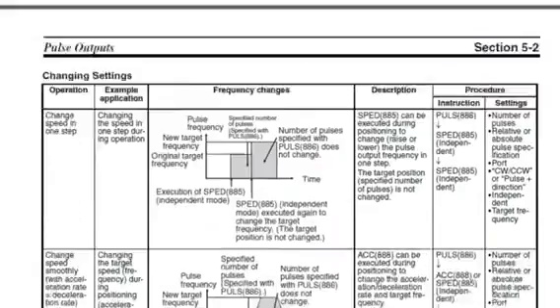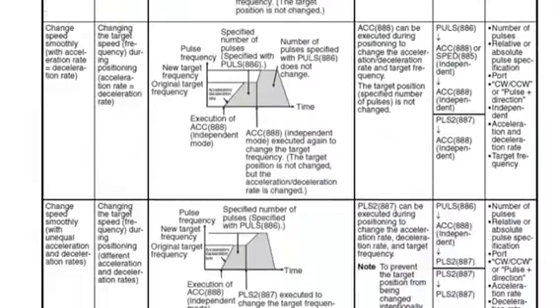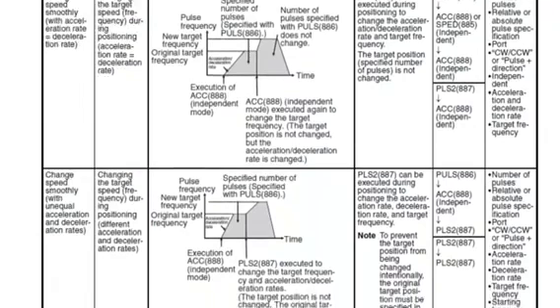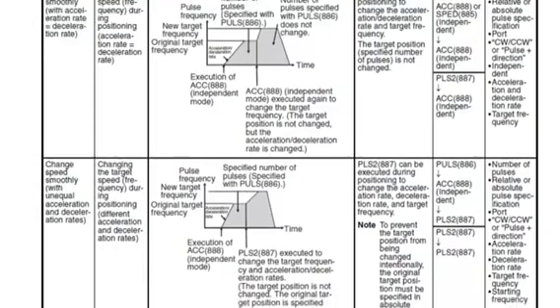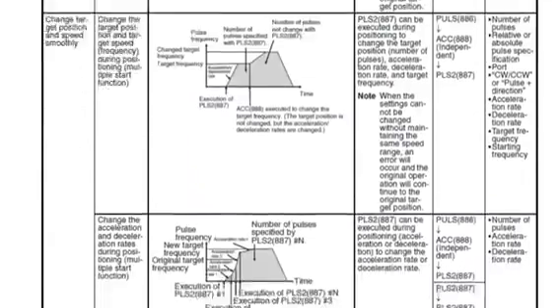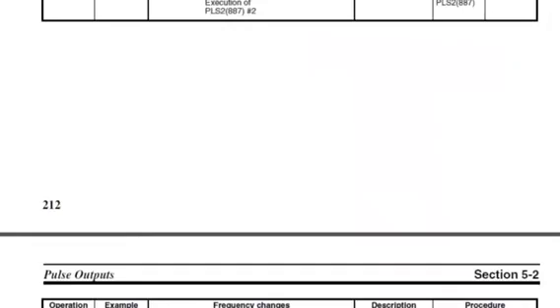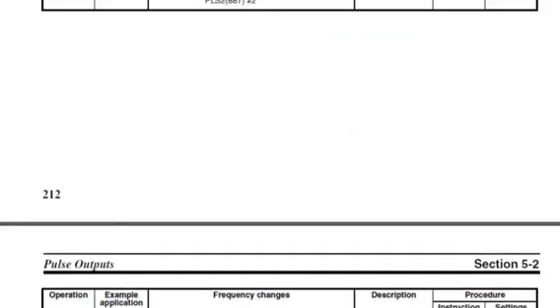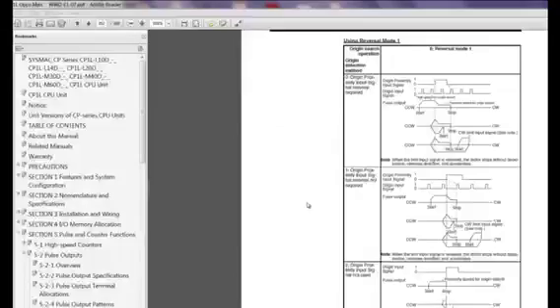You can create a step frequency if you're trying to get through resonance on a stepper motor. You can then in the next operand set your accel, your overall, or your speed, your overall distance at decelerate. And that instruction does it all just in one PLC block. A very nice instruction to keep things simple and compact. There are a few other explanations in here, changing speed and steps, blending to change with an accel, and things of this nature. There's five or six pages in here that do a pretty good job of explaining this. This will be in the ops manual for the CP1L.